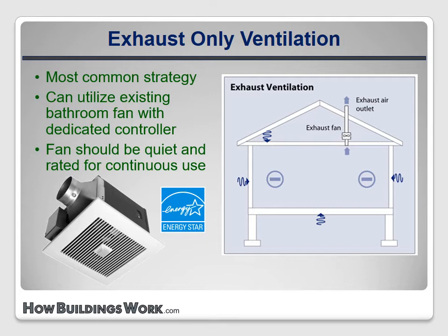In this case, they have two applications. They need to provide that high flow for local exhaust and lower flow for whole building exhaust. The low flow can be accomplished by a control system that either cycles the fan off and on regularly or turns down the speed of the fan. Some fans are available with integral ventilation controls. With other fans, the switch must be replaced by a specialized controller. We'll come back to this later in the lesson.